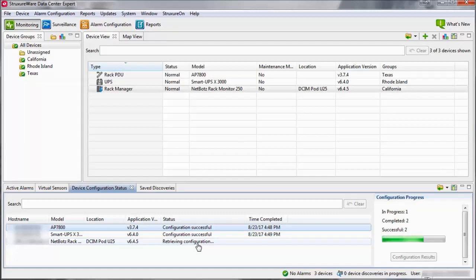Note that if the FTP or SCP settings have been changed, Data Center Expert may be unable to verify the changes. If Data Center Expert was unable to connect to some of the devices, ensure the device file transfer settings and settings on the device are correct.